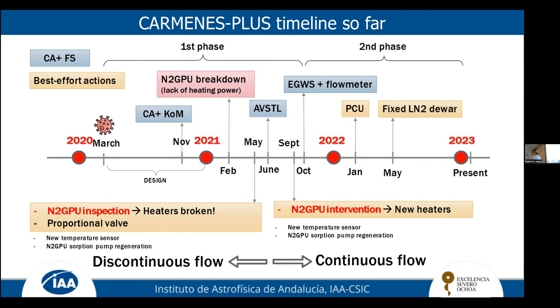At the same time, we placed what we call a proportional valve. Remember I told you we were working with an on-off valve. Basically, with an on-off valve we have what we call discontinuous flow because you're opening and closing with no other states in between. But with a proportional valve, we have as many states as we want between 0 and 1, so we have a continuous flow.